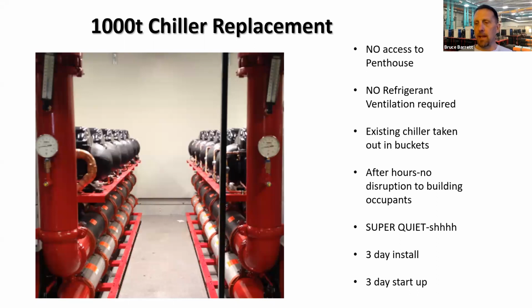Another example of just about every component of a modular chiller retrofit is a 1,000-ton job we did. Pershing Square, I believe, is the 17th floor penthouse, had a very, very large existing chiller. These 80-ton modules were brought up through the service elevator, stacked in the mechanical room. Very low refrigerant charge, did not need ventilation.